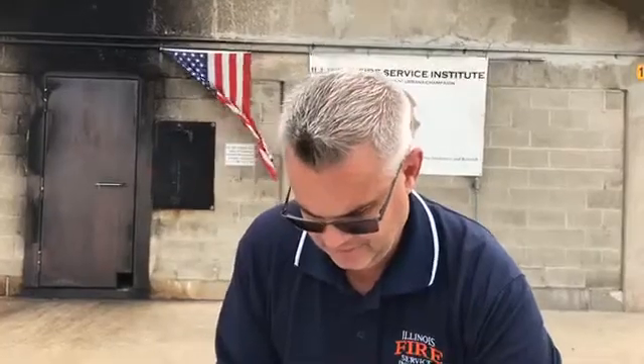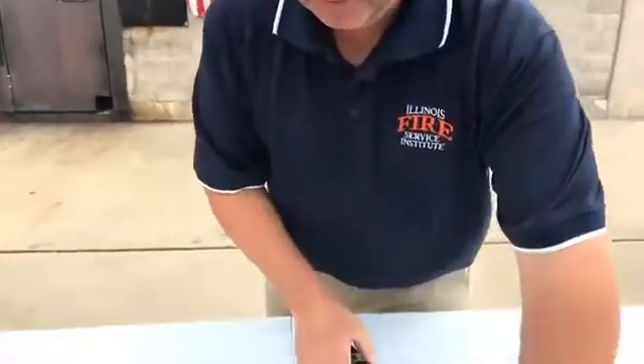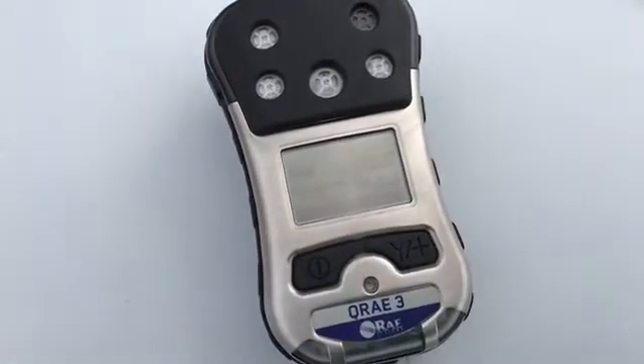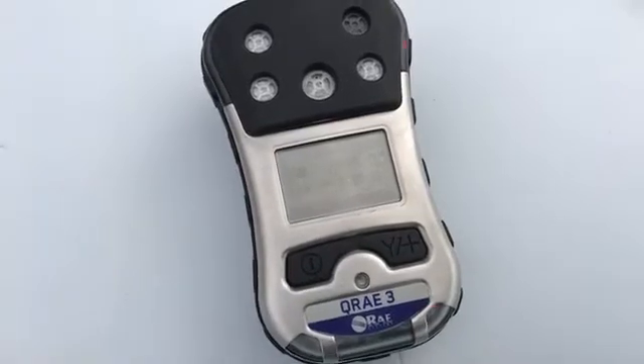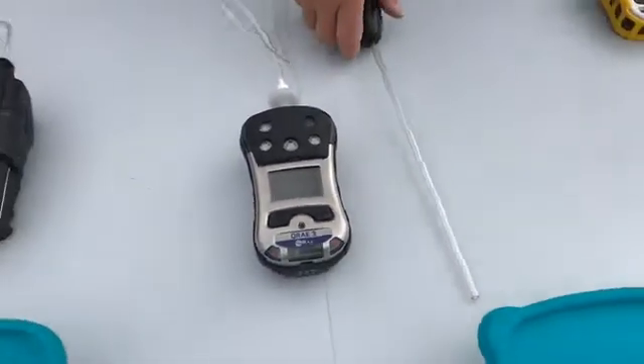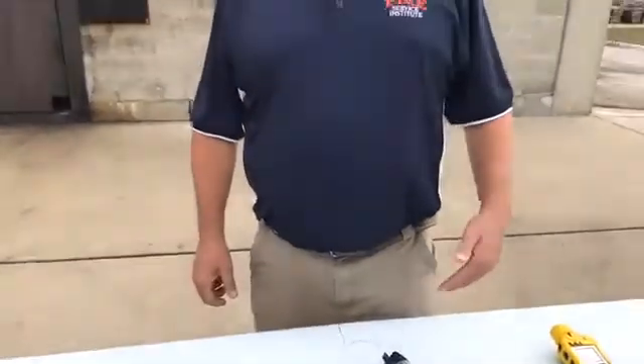So we're going to go ahead and do that a second time just so you can see it react. And again, we got that alarm on the lower explosive limit. So what's alarming is the explosion sensor, and it's alarming at what we call the LEL, or the lower explosive limit of the product. So it's seeing enough product where it's in the alarm mode of that LEL sensor. Again, we don't know specifically what the product is yet or how much we might be dealing with, but at least we know that the monitor's seeing it, and then we need to react to that problem that we have.